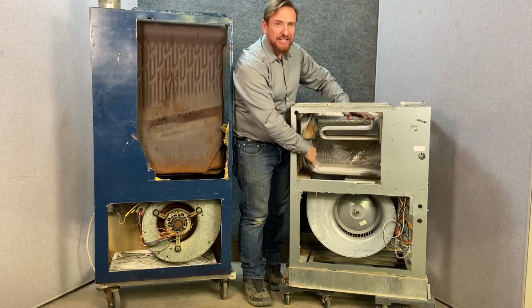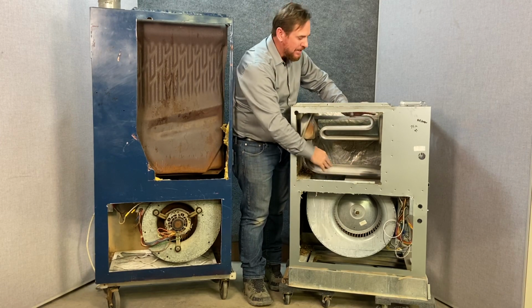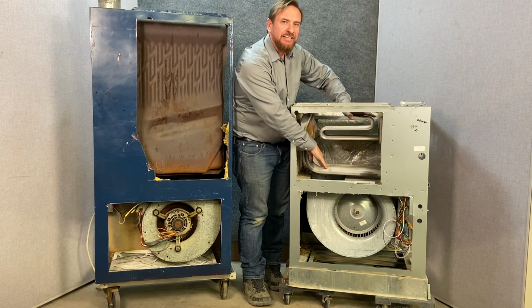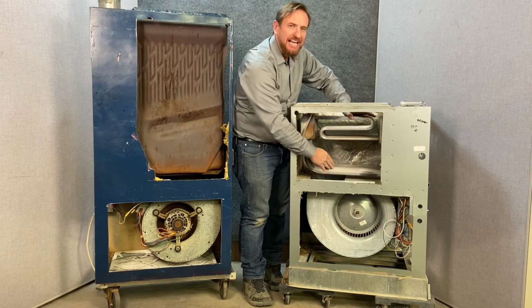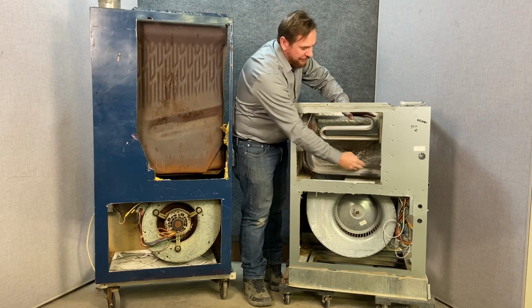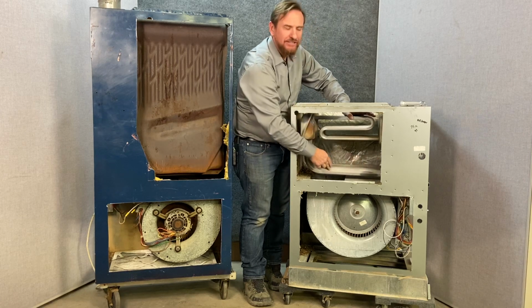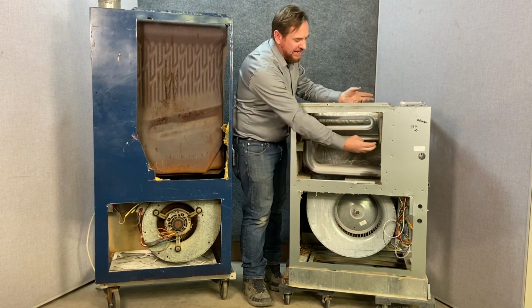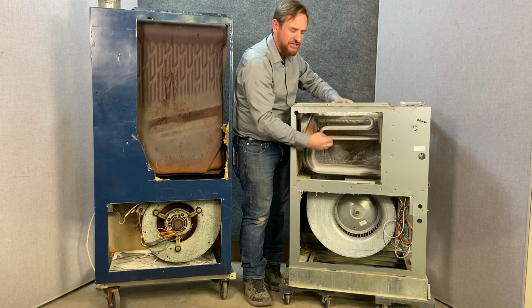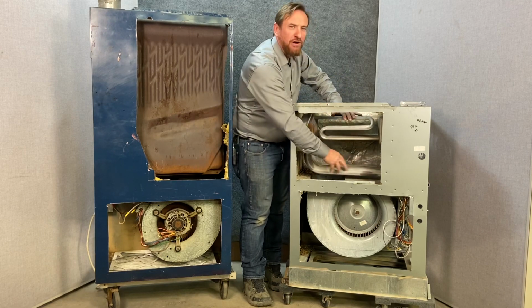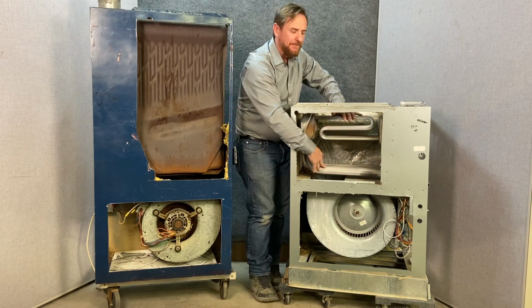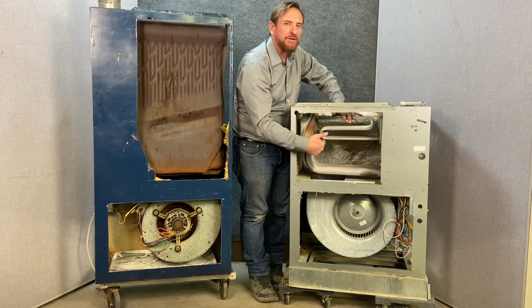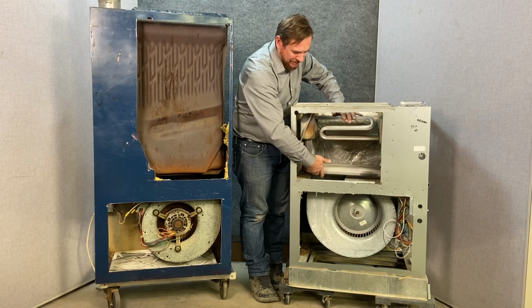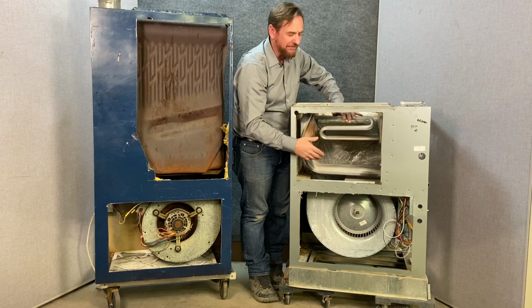Now, this heat exchanger has a special coating on it. Usually it's a type of galvanized. They even made some that were stainless steel, but even the other ones didn't rust out nearly as bad because the flame wasn't actually touching against this metal. The flame was directed to shoot inside this tube, and because this inducer fan is pulling a draft through this heat exchanger, the flame would just brush against the side, so it didn't burn out. Sometimes people wouldn't set the gas pressure correctly, and it would cause these tubes to burn out. That's definitely going to be an issue.